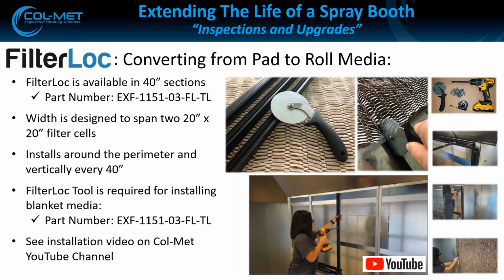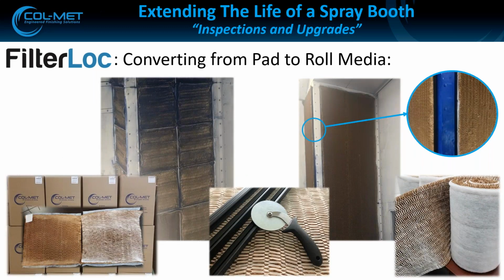That's where the FilterLoc comes into play. It helps with those gaps, because a 20 by 20 pad, even installed properly, has potential for 20, 40, 60, 80 linear inches per pad for bypass. With the blanket system, we close in that whole thing. There's no place for bypass except through the media.